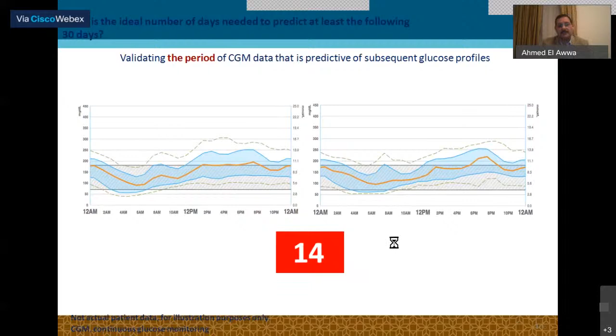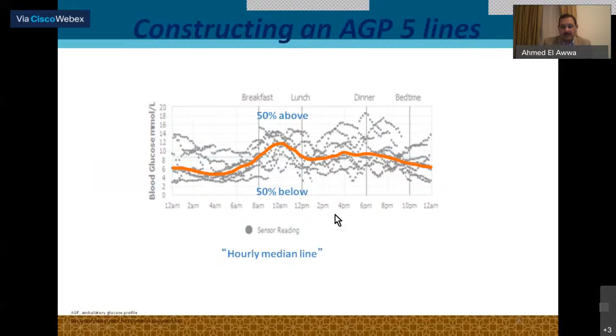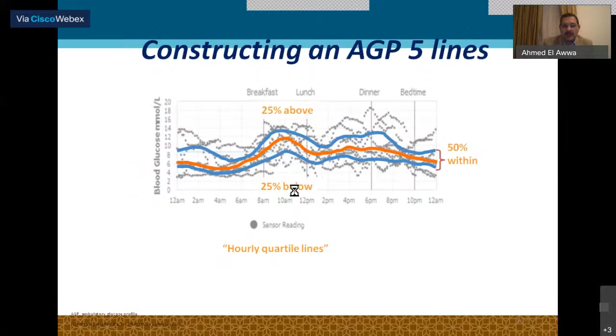This is what they call the ambulatory glucose profile, and it is the way they present the data in a graph in most of the sensors now. The download, the look of the page might change from one device to another, but most of them will have the same graphs. So this is one example where you can collect the data from 2 weeks as discrete data. Each dot means one sensor reading, and the readings are every 5 minutes, or every 1 minute in the recent sensors.